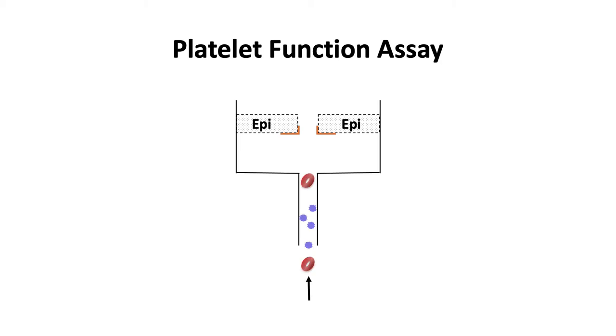Next, citrated whole blood is introduced at high shear rates. When platelets encounter the agonists, they become activated, forming a platelet plug. This platelet plug blocks flow in the tube. The time it takes to stop blood flow is reported as the closure time in seconds.